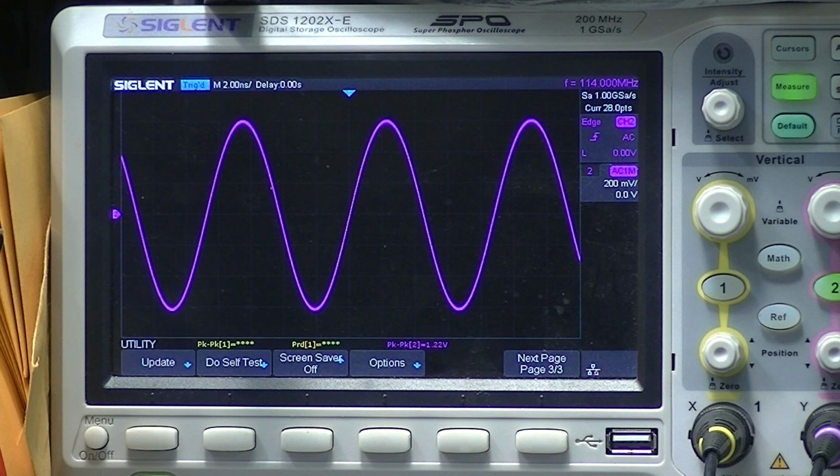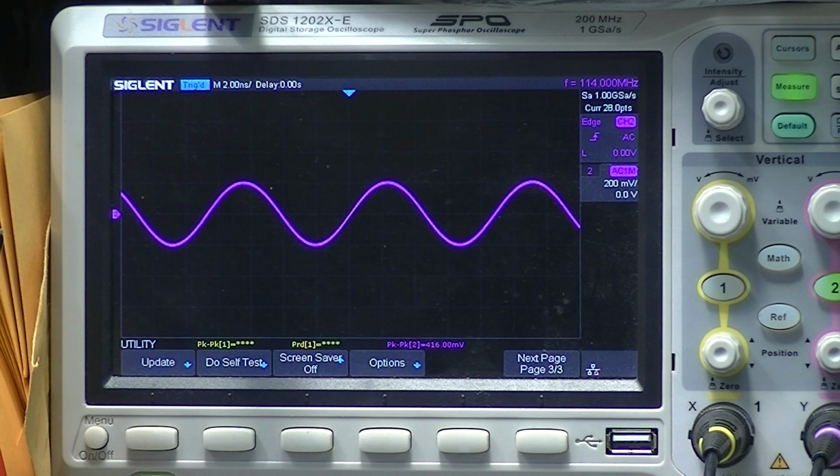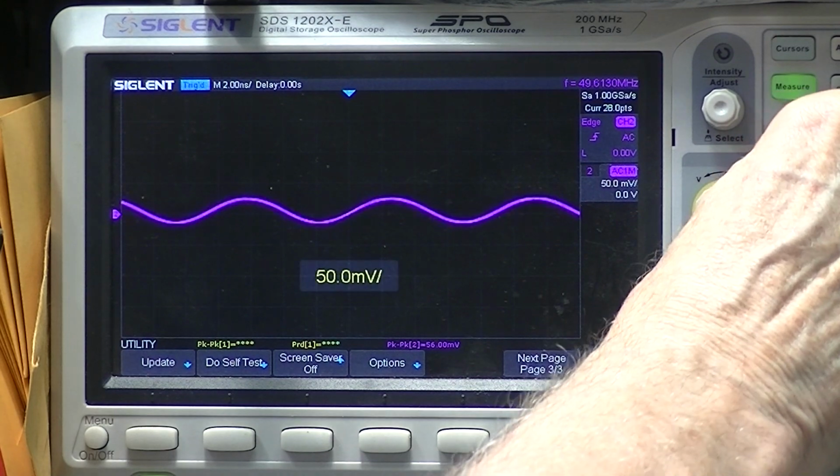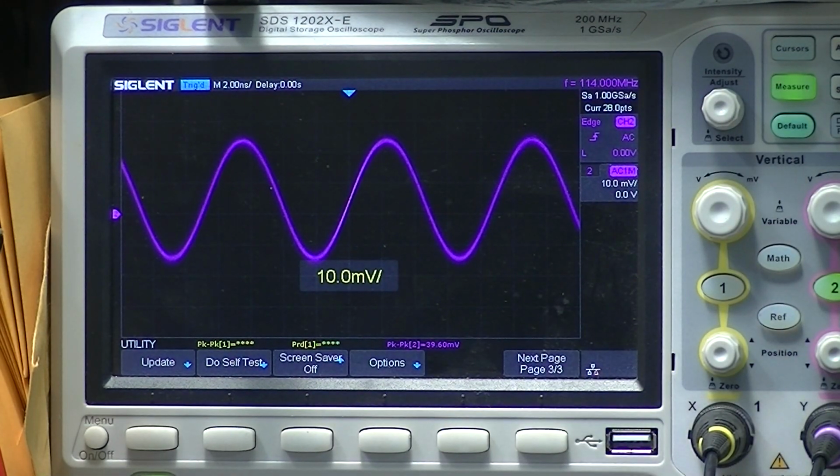I can also insert 10 dB of attenuation. There's 10 dB. There's 30 dB. I cannot attenuate in any finer steps than 10 dB. The output can be 0, minus 10, 20, 30, 40, 50.